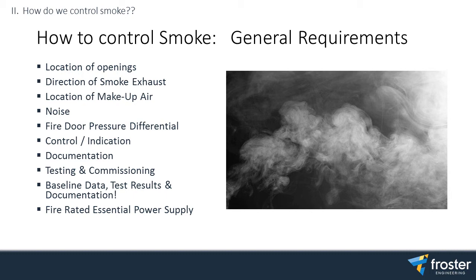I've been in situations where we're trying to find a makeup air path, but we don't have many options. If it's greater than 2,000 liters a second on a smoke exhaust, you need 6 meter separation. And if I'm given a plan and I don't have that many options, then what it typically does is it forces a higher cost. I have to run the ductwork a longer length, which is adding unnecessary cost to the project.